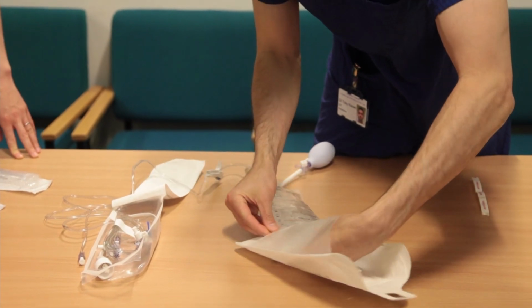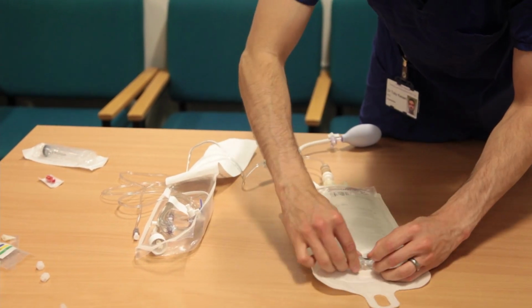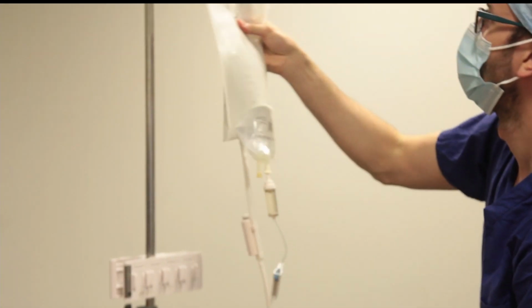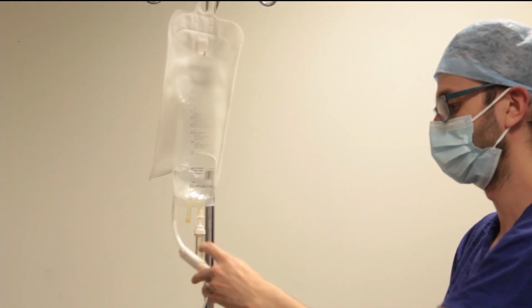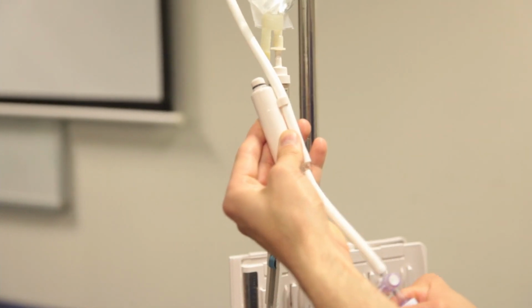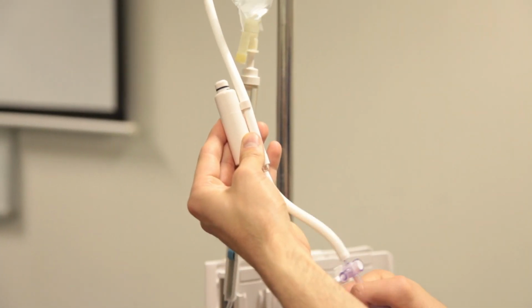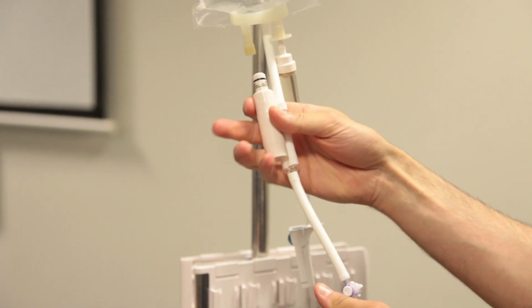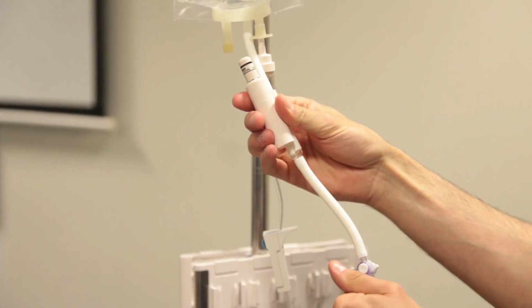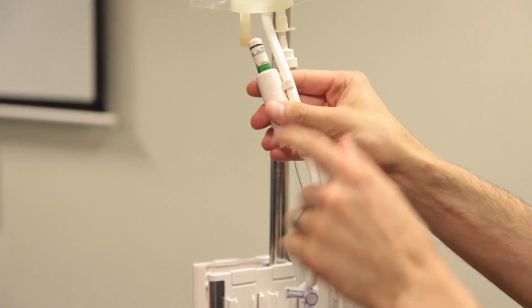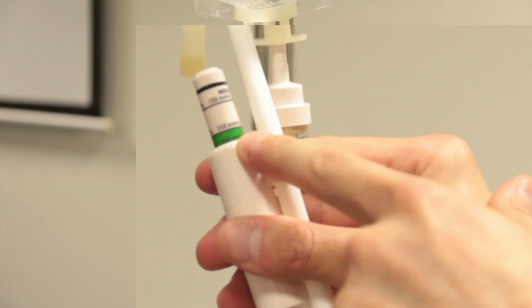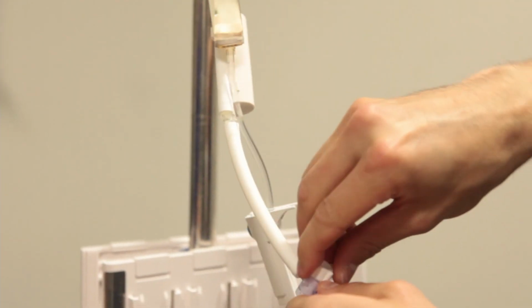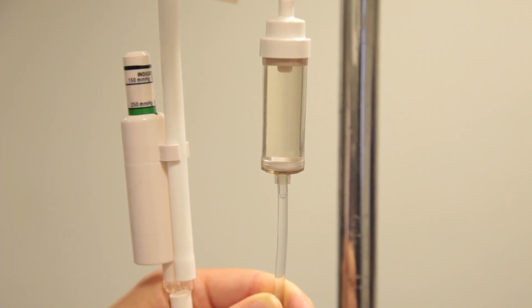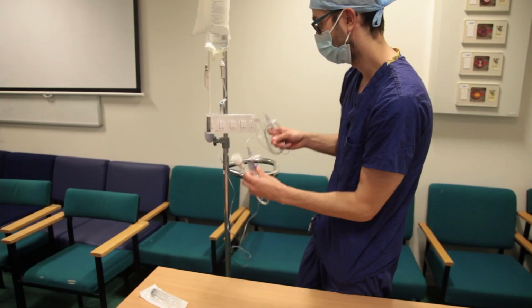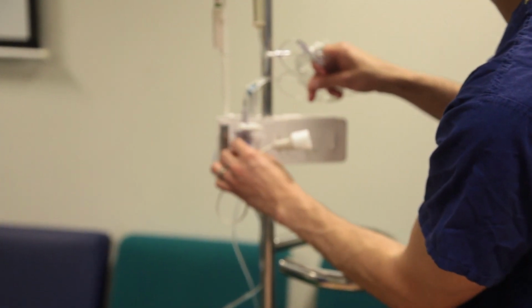Insert the saline into a pressure bag and then inflate the bag until the pressure indicator is green. At this point, rotate the off arm on the three-way tap upwards towards the bag, and this will avoid it deflating. Over time, the bag may still gradually deflate and need more air to maintain the pressure gauge in the green zone.